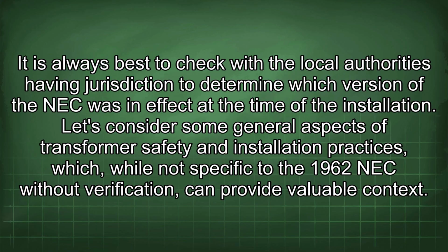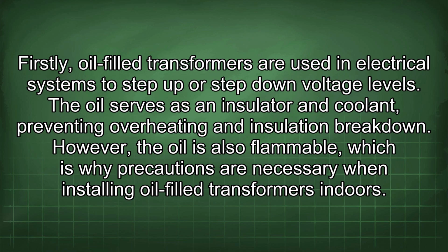Let's consider some general aspects of transformer safety and installation practices which, while not specific to the 1962 NEC without verification, can provide valuable context. Firstly, oil-filled transformers are used in electrical systems to step up or step down voltage levels. The oil serves as an insulator and coolant, preventing overheating and insulation breakdown. However, the oil is also flammable, which is why precautions are necessary when installing oil-filled transformers indoors.